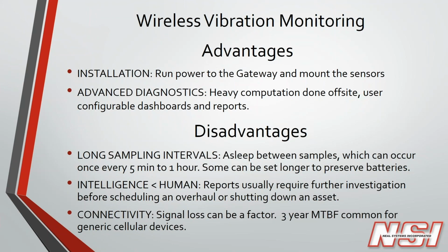And so the last disadvantage that's important to mention is connectivity. So signal loss is almost always a factor with any cellular device. And a 3-year MTBF is common for generic cellular devices. And that just basically means if you've got 3 of any type of cellular device, and that includes your phone, operating for a year, you're likely to have at least one communication issue over that time. And that would be considered pretty reliable for cellular.